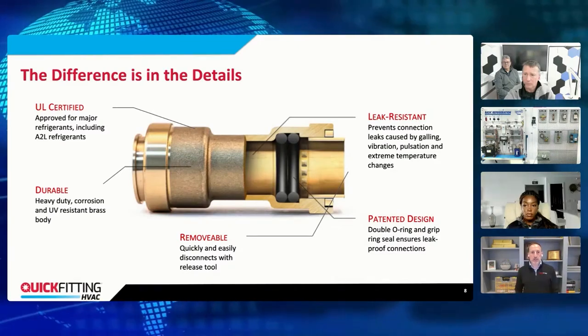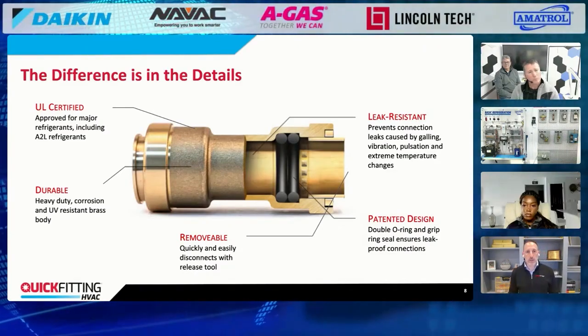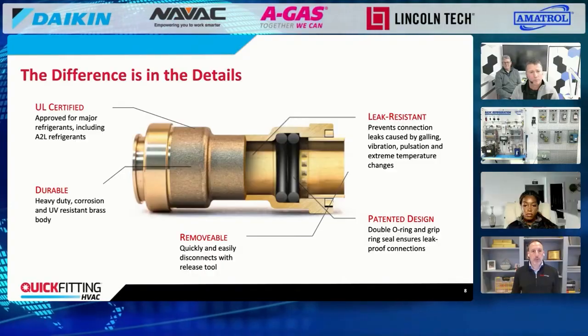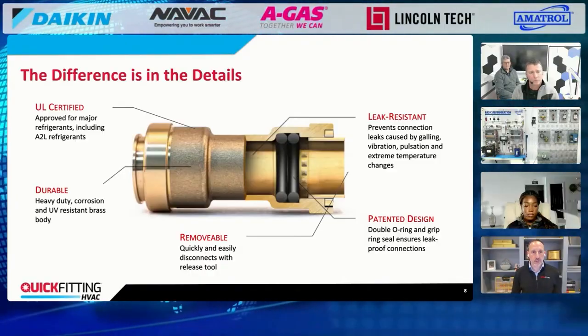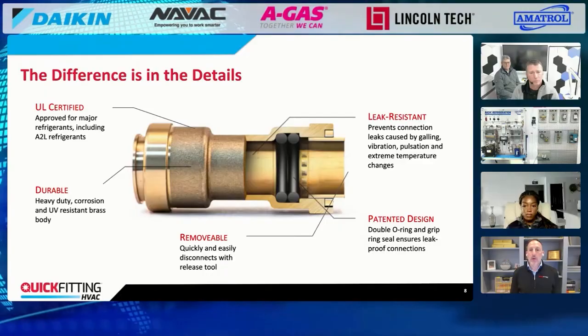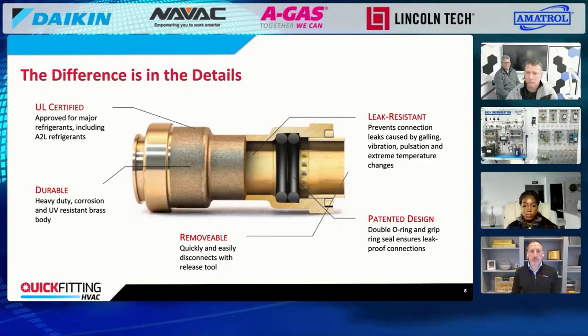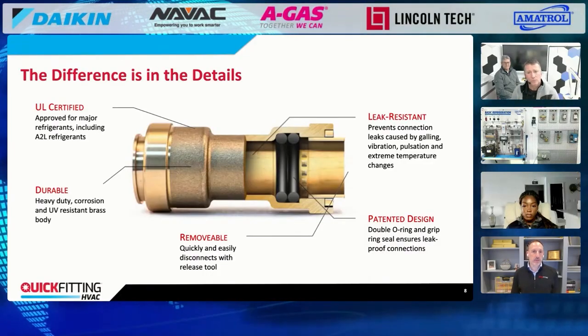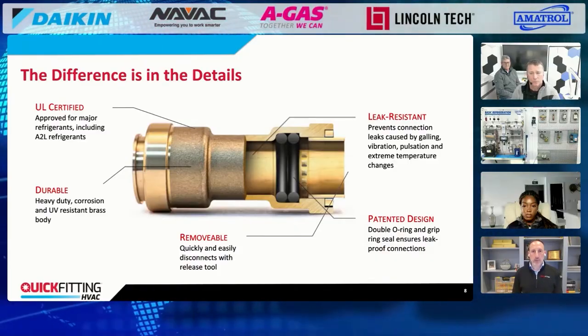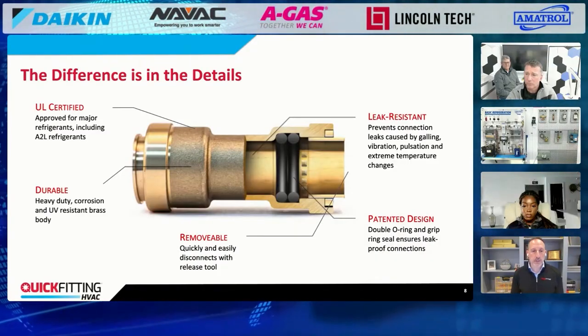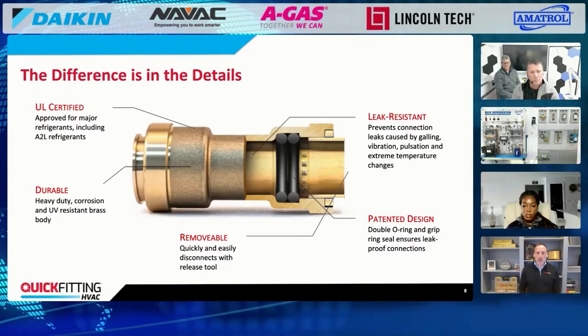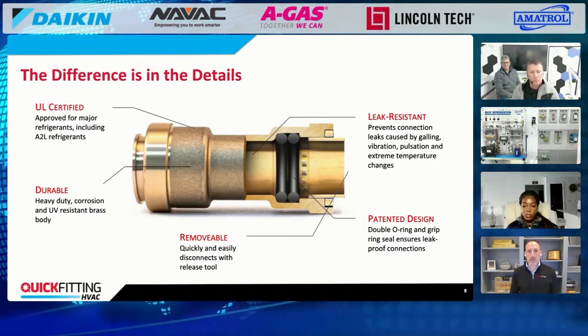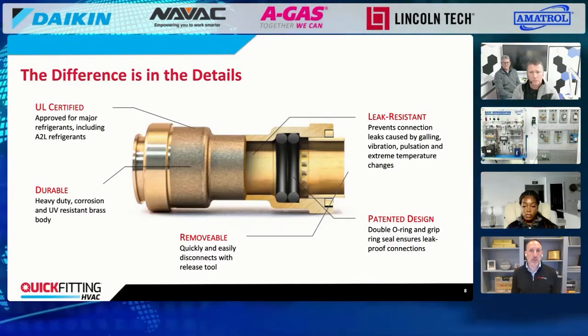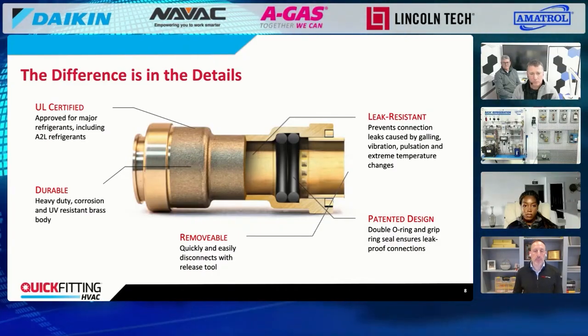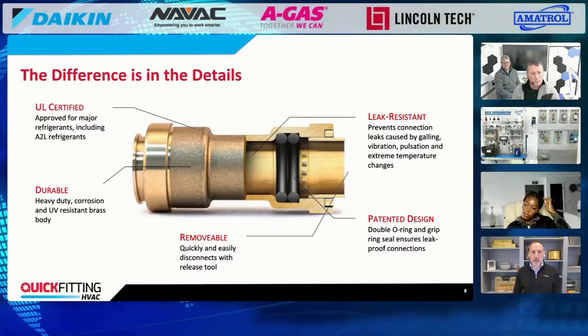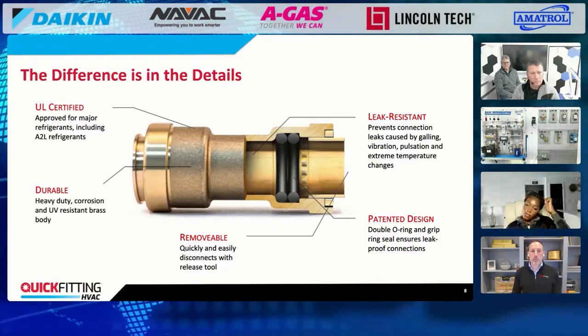With push-to-connect fittings, you're really looking at that O-ring. Towards the right of center you see two black rings in the cutaway—that's what makes your seal. Those O-rings are fit specifically to the pipe size, so a 1/4 inch pipe has an O-ring diameter fit for 1/4 inch pipe. We have a patented design with two O-rings, giving a bit more safety factor, so you get a reliable result every time. Just to the right of the two O-rings, there are steel grip rings that hold the pipe together.